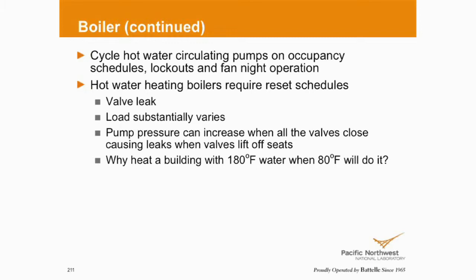And a lot of people kind of tend to overlook this, but differential pressure control on your hydronic loops is critical. Most valves have a pressure rating, and if I'm running 55 psi out, come back at 35, 20 psi differential, that 55 might be higher than what the valve is rated for per the manufacturer. So again, recommend that you look at what your pressures are in a closed loop and see if you're exceeding the vendor's maximum pressure on the valve, and see if that's why you got valves that are leaking. I've seen people go to the trouble of replacing valves because they were leaking, they thought, and then they put in a brand new valve and it's still leaking. Well, your hydronic loop pressure is running too high.